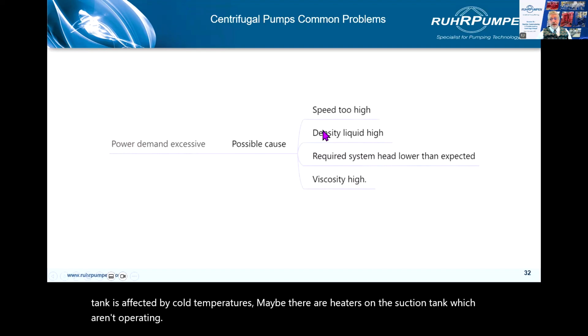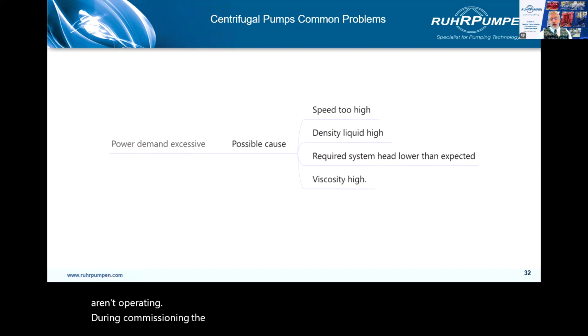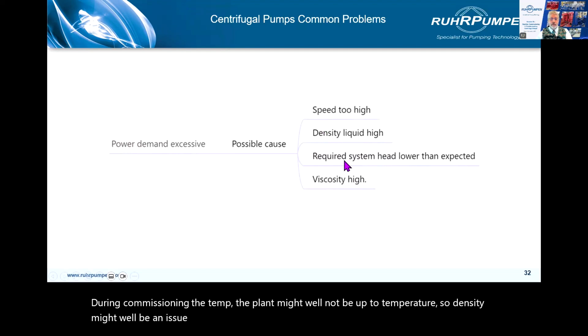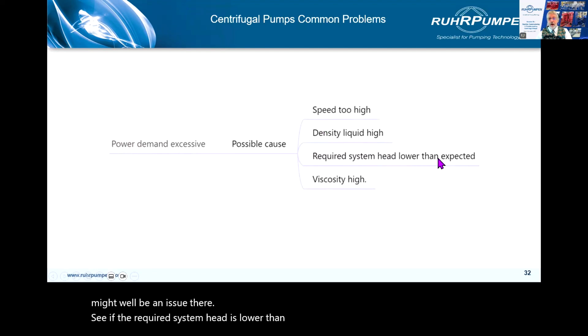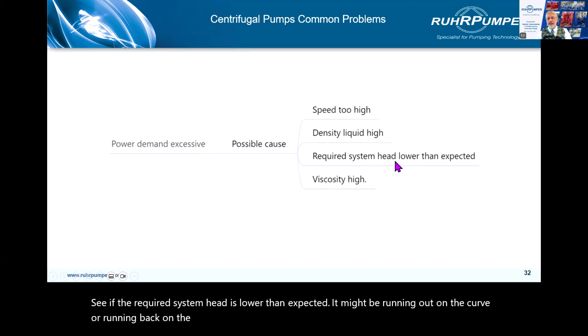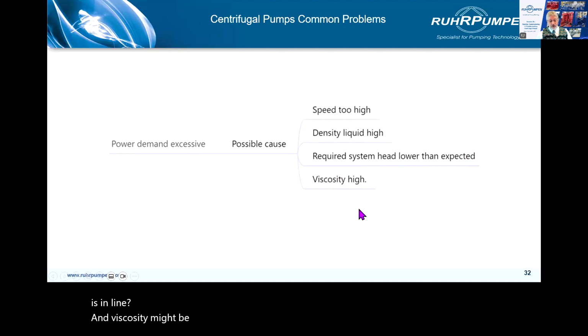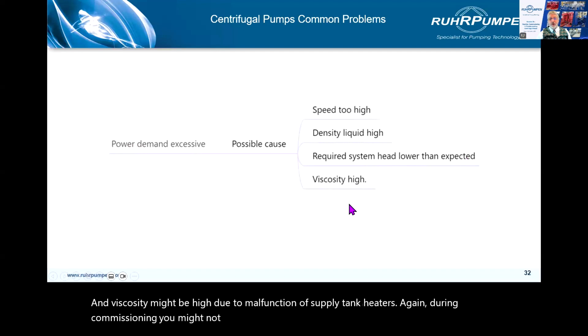During commissioning, the plant might well not be up to temperature, so density might well be an issue there. See if the required system head is lower than expected. It might be running out on the curve or running back on the curve, depending on what downstream equipment is in line. The viscosity might be high due to malfunction of supply tank heaters. Again, during commissioning, you might not be at full temperature, so density might be high and viscosity might be high.